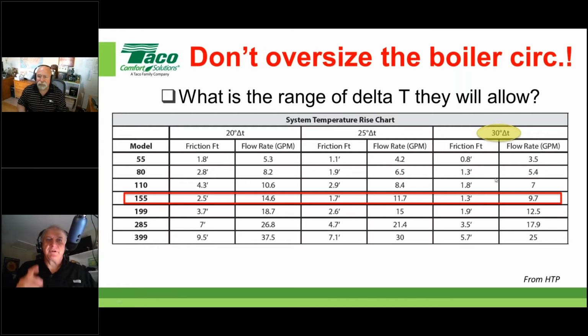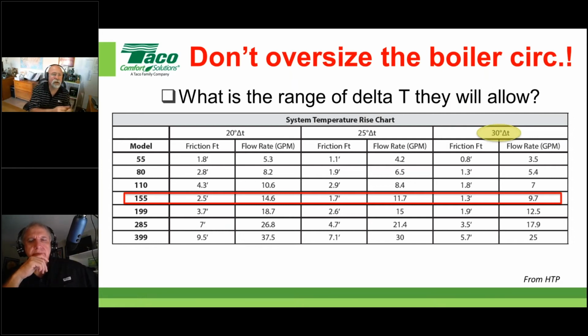It's so important to note that that's not the delivery side delta T. That's the boiler side delta T. Let me make that distinction, because we're sizing the boiler primary circulator. Good point, John. Yeah, we're talking about the circulator for the boiler. The system can run at a 10-degree delta T. We don't care. We're sizing for the boiler.